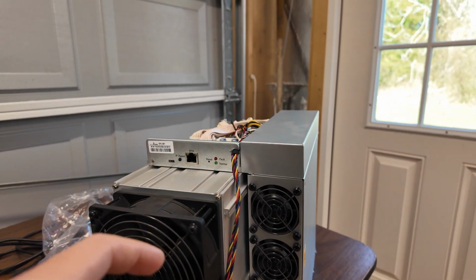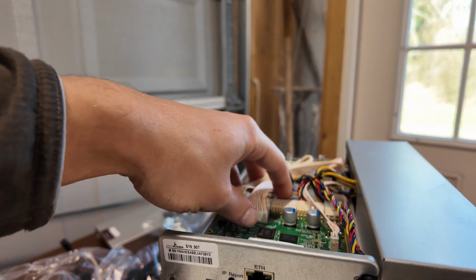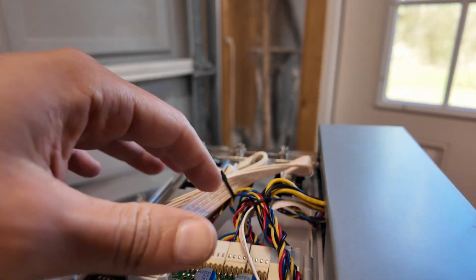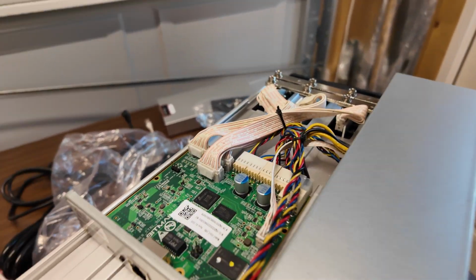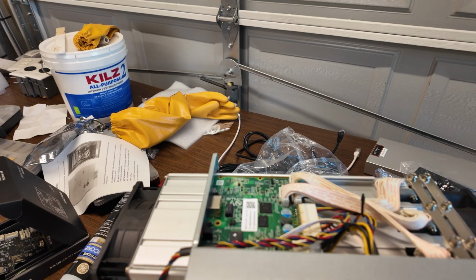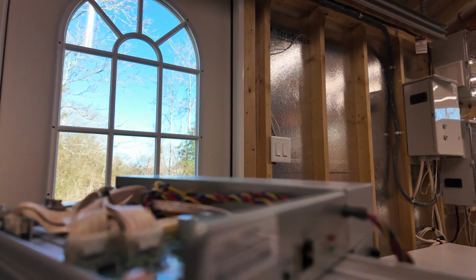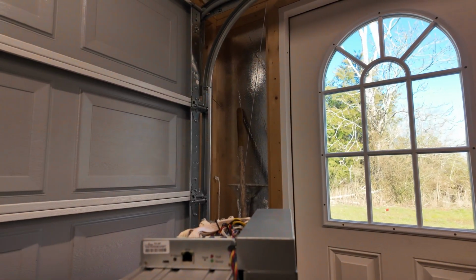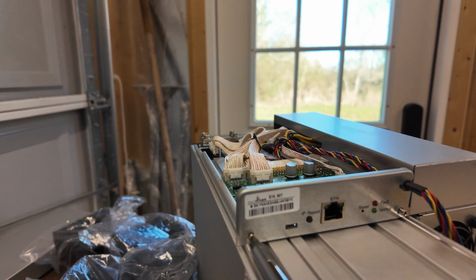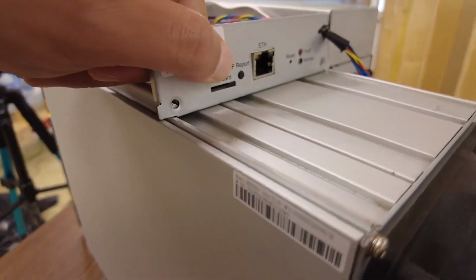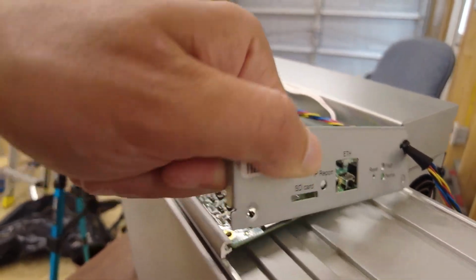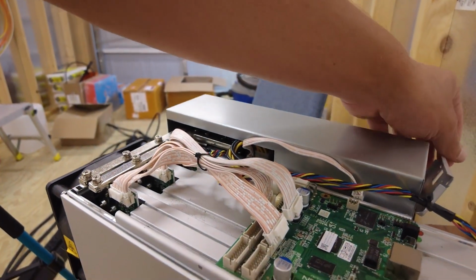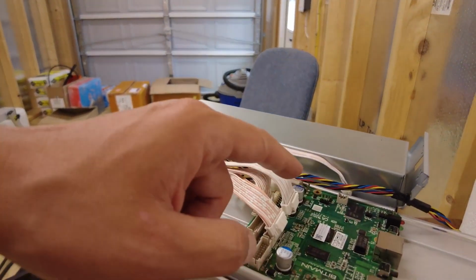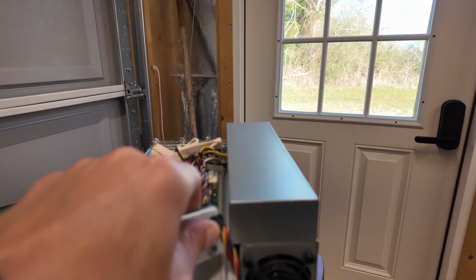So there's a couple ways to go about this. Pretty much this control board is only in here with tension, and it slid into place. When you really look at the board, there's no screws going into the device or anything like that. It slid into this rail on both sides right here. So we're just going to pop this faceplate off, slide it right out. Now, just taking a screwdriver or drill, removing those screws. Look, it comes right off. It's actually zip tied to the fan power cable, which is that multicolored cable running up. So now we'll just push this out. And now you can easily see what I'm talking about.